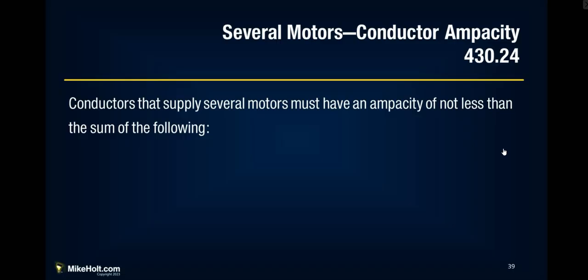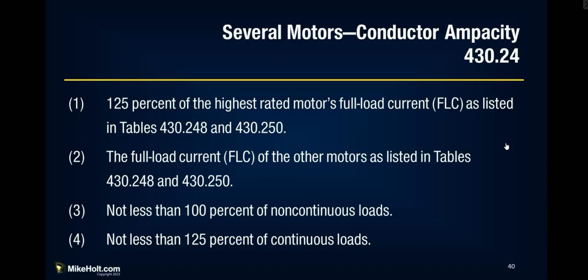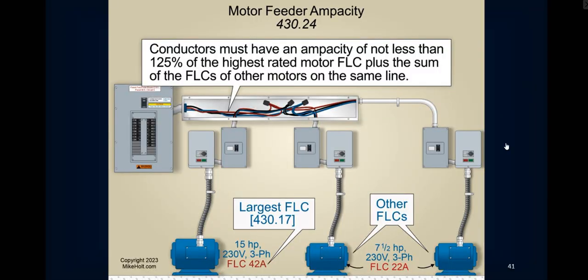That's the difference. But 430.24, several motors or motors and other loads. So this is the caveats for this. 125% of the highest rated motor FLC. Essentially what this is saying, you've got several motors, and good, they do give me a slide for this. So check out this graphic. You've got a panel that's feeding all this. You jump out and hit a trough. Now you're dropping down, and you have your overcurrent protection device for each one of these motors, and then you've got your motor starter there next to it, and then flex coming down to the motor. So you can get the picture here. But you're feeding this all with a subfeed and then splitting out from a trough to each one of these motors. How do you size those conductors?